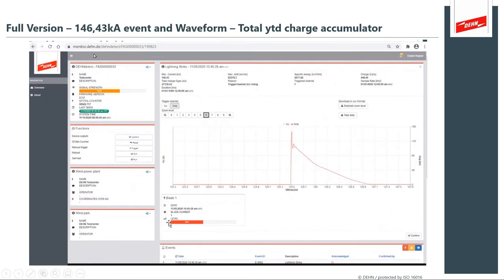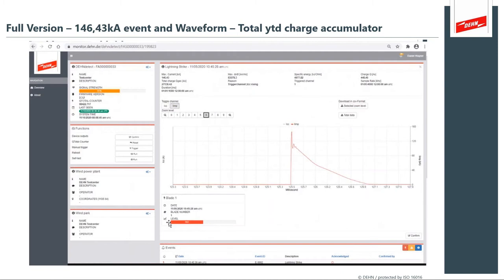Here's an event that was captured — an incredibly high event at 146 KA. It tells you when it occurred, gives you a waveform of the event, tells you the amount of charge and the accumulated charge to date. It tells you what happened, precisely which blade was struck, what the blade detector saw, and integrates all that information with the Rogowski coil data. It really gives you a great snapshot of that event for later analysis.